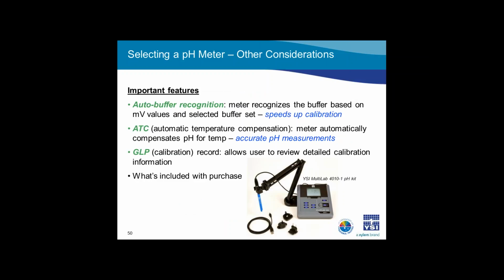Now that you have a meter selected, ensure it has other important features before making a purchasing decision. Auto buffer recognition speeds up calibration by automatically recognizing the buffer being used. Automatic temperature compensation is very important, as this feature takes the temperature reading and automatically compensates pH measurements for the influence of temperature. A detailed calibration record, also called a good laboratory practice record, allows the user to view important calibration information such as the slope, 0 point, millivolt values in each buffer, and temperature for each calibration point. Also consider what is included when you purchase the meter, such as an electrode stand, power supply, and other accessories.